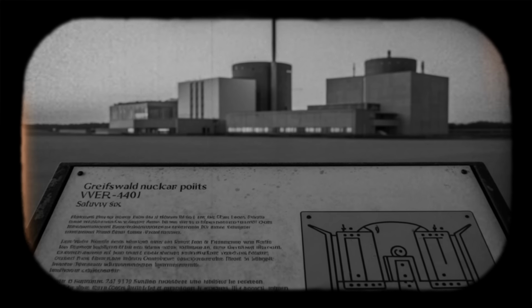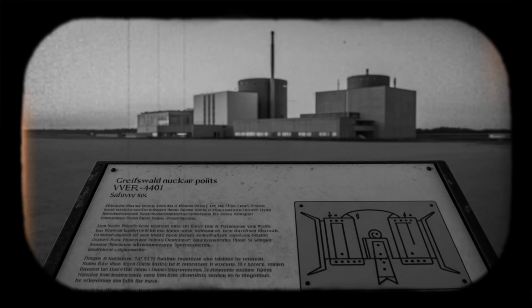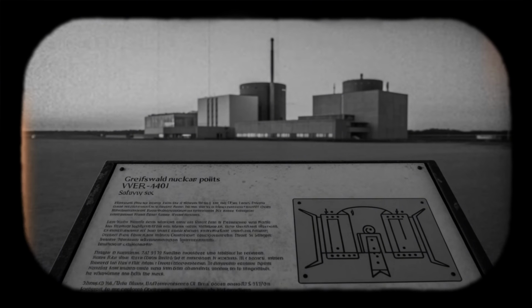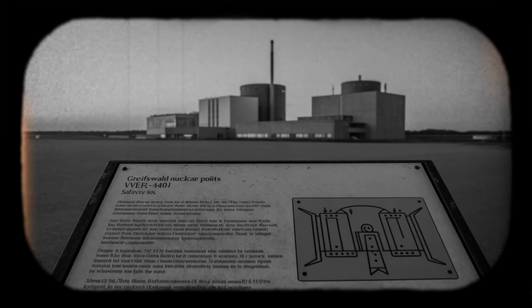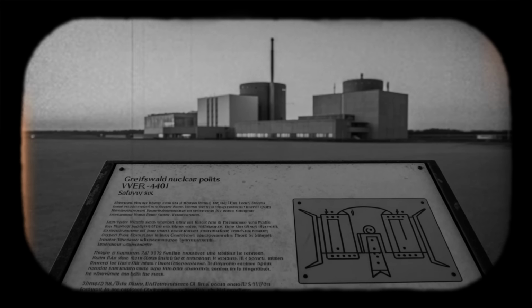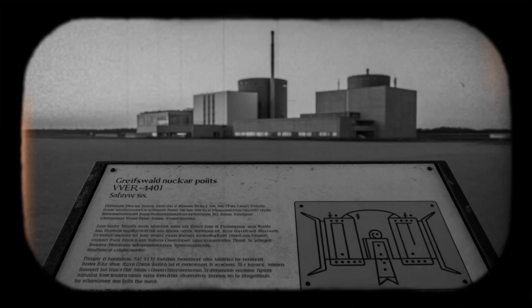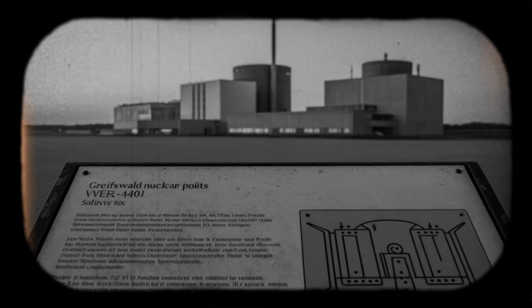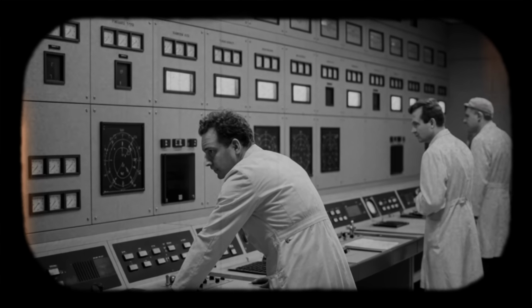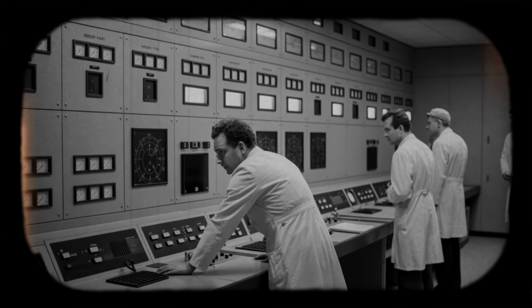Attempts to start the emergency diesel generators revealed the full extent of cable damage. 3 EDGs provided backup power for Unit 1. Design basis: at least 2 should survive any single fire or equipment fault, preserving redundant injection and feedwater capability. Reality: control and auxiliary cables for 2 of the 3 diesels were destroyed in the common duct. Only 1 EDG could be started and loaded. The Nuclear Energy Agency reconstruction noted this as a critical limiting factor. Reduced emergency power capacity constrained operators' options for restoring cooling systems.